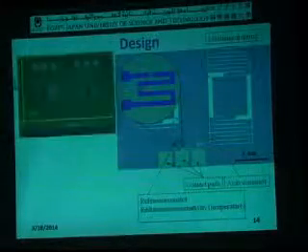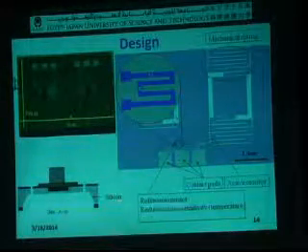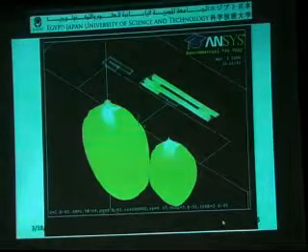And actually the size of this sensitive part is about 4 micrometers. And we already fabricated the sensor with 5 millimeter, with 6 millimeter. The fabrication process is very sophisticated. It consists of silicon and thermal oxidation, ion implantation, aluminum metallization, isotropic etching, deep reactive ion etching, very sophisticated process.